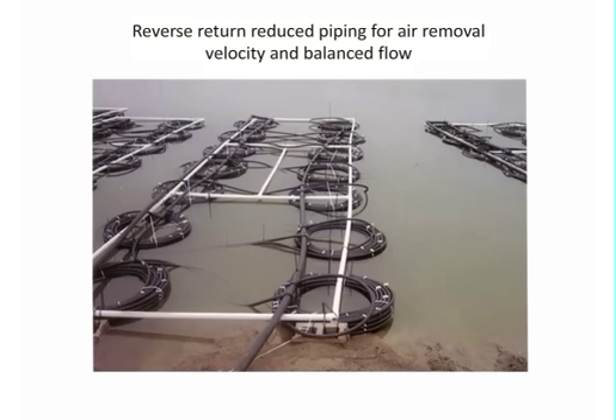Here's an example of a large commercial project. You can see reverse return manifolding. This is crucial when you're using spaced coils to ensure good air removal, always a part of any loop design, and for balanced fluid flow so each circuit gets the appropriate flow evenly dispersed throughout the loop array.